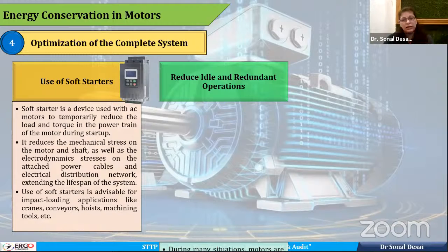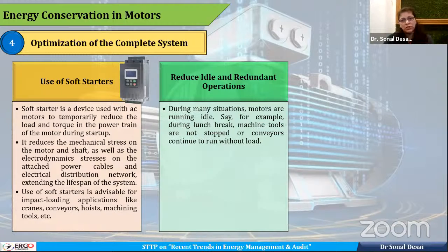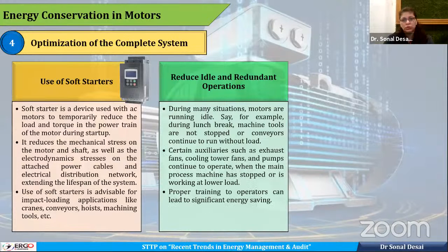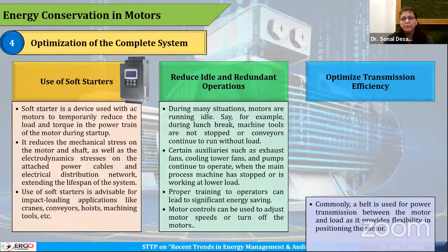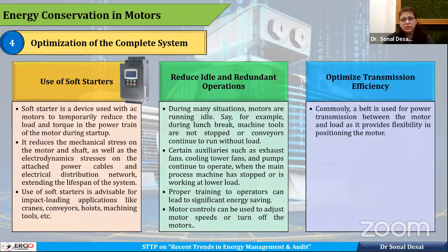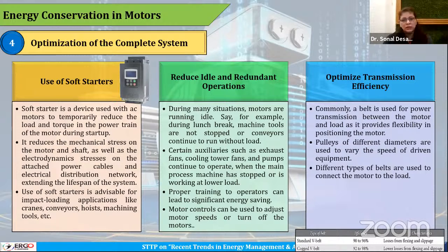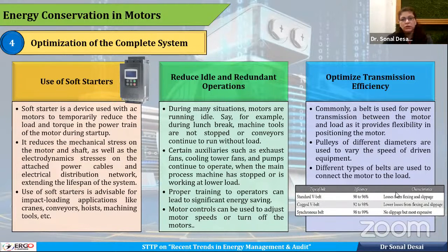Reduce idle and redundant operation. Many times we have seen that in a lunch break or in other breaks, operators just keep the motor disengaged from the load and keep it running. So that will also consume power. So monitor those types of applications. And optimize transmission efficiency. Go with a good quality belt rather than a standard V belt. Go with the cogged V-belt or a synchronous V belt. So they will have a better efficiency compared to the standard V belt.